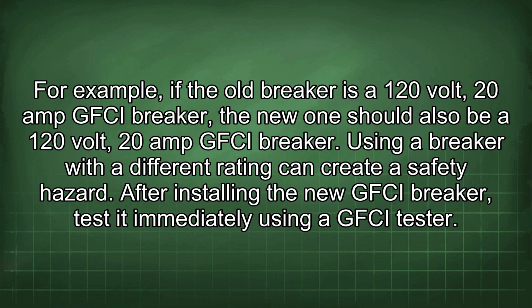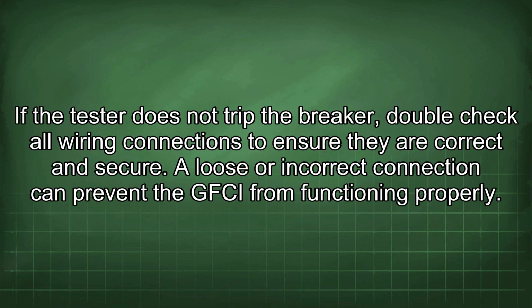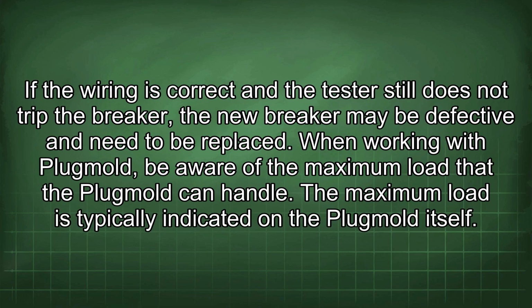After installing the new GFCI breaker, test it immediately using a GFCI tester. If the tester does not trip the breaker, double-check all wiring connections to ensure they are correct and secure. A loose or incorrect connection can prevent the GFCI from functioning properly. If the wiring is correct and the tester still does not trip the breaker, the new breaker may be defective and need to be replaced.